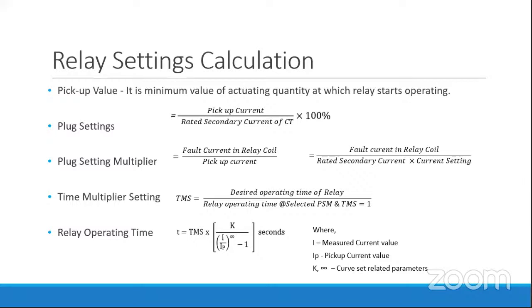Relay operating time means at what time the relay will operate. If we are giving certain time intervals, then for a certain value of fault current, how much time will the relay take to operate for that particular fault current. For this there is an equation: TMS into K, which is the constant related to the curves, divided by (I by IP) raised to infinity minus 1, where I by IP is the measured current divided by the pickup current.